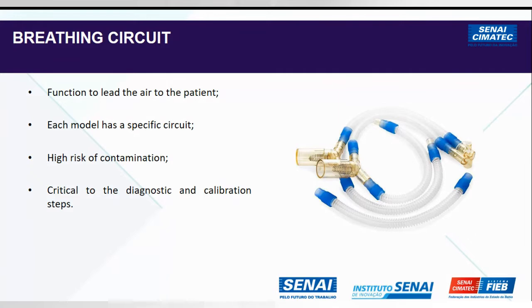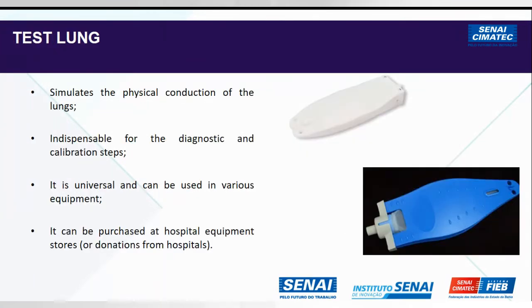As Rodrigo said before, it is critical for the diagnostic and calibration steps. You need to put the ventilator to operate the same way as if it operates on the patients, because that's when you need the breathing circuits and need the test lung, which simulates the physical condition of the lungs. It's indispensable for diagnostic and calibration steps, and for maintenance. You simulate the ideal conditions of patients. The test lung is universal. You can purchase it in hospital equipment stores or get it by donation for the hospitals.